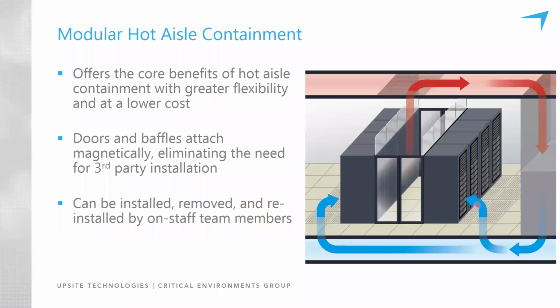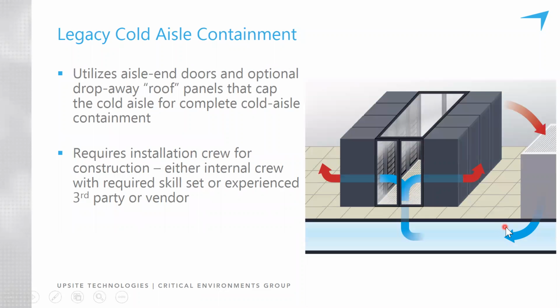When we look at legacy cold aisle containment, the reason that this generally isn't as efficient is that the rest of the room becomes hot. We're fully containing the cold air in the cold aisle, and when you open the door to a room with cold aisle containment that's done very well, it may be 90, 100 degrees as soon as you open the door. And a lot of people are not willing to live with that experience or work in that environment. And so while cold aisle containment is more popular because it's easier to deploy, it's often not done as well, meaning it's not fully optimized. The environment is not taken to the potential that it's capable of.